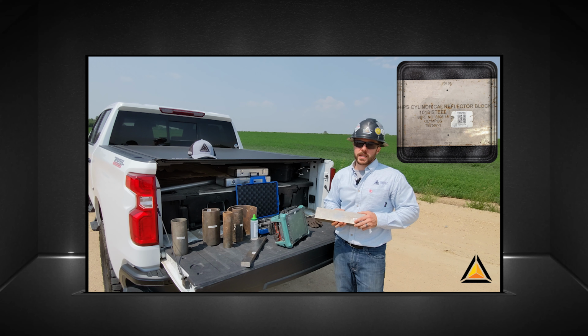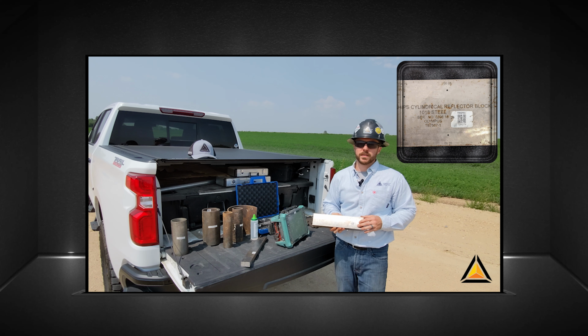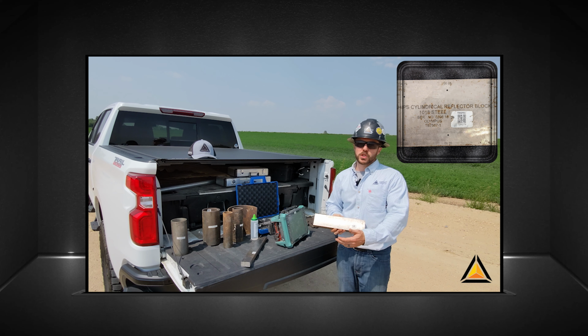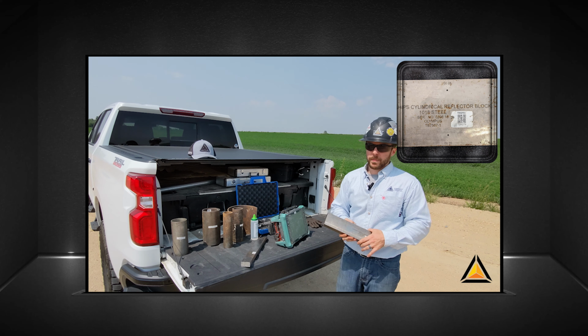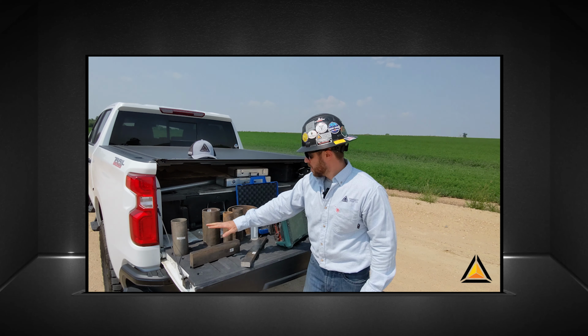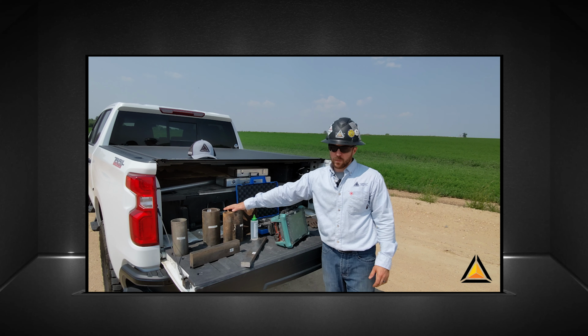Now, this is a NavShips calibration block that has side-drilled holes at different depths across the face, used for distance, amplitude correction and sensitivity. This ensures that the sound being transmitted into the material is returning to the probe at the correct timing. Once that calibration is done, we move on to the material-specific calibration.